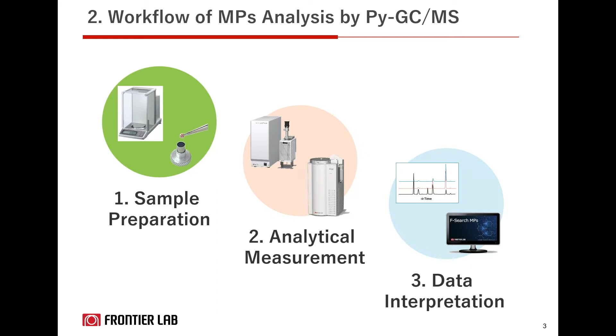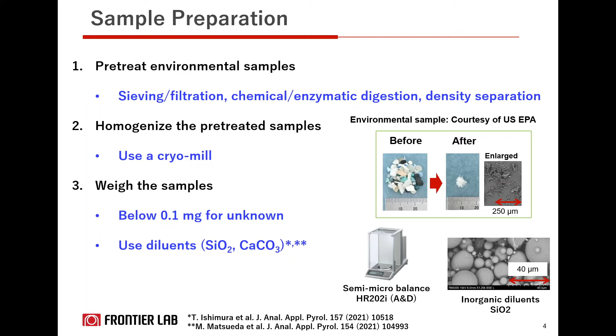So in terms of sample preparation, microplastics are typically extracted from environmental samples by performing appropriate pretreatment and then homogenized using a grinder or a mixer. Then you can place your unknown sample or the standard sample into your sample cup and weigh it using your microbalance in most cases. However, as part of our calibration kit, you get the diluents of SiO2 and CaCO3, which you can see here, that they allow you to eliminate the need to have a microbalance. So you can use a semi-microbalance and prepare your own calibration standards to measure small amounts of samples as well. So the SiO2 and CaCO3 diluents have a similar functionality to solvents in terms of sample preparation. In simpler words, if I want to really describe the functionality of them, I could say that they are your solid solvents that you can really use for creating your calibration curve.